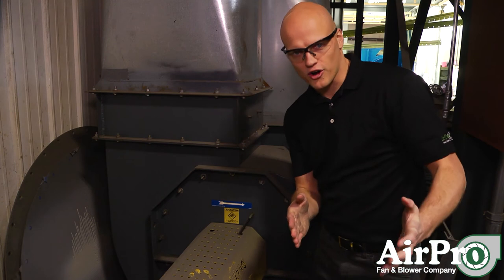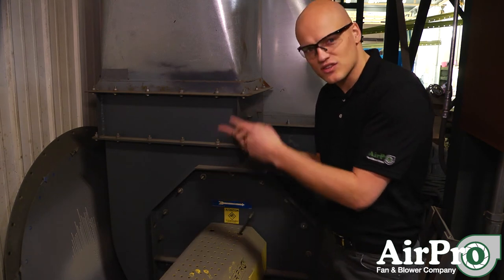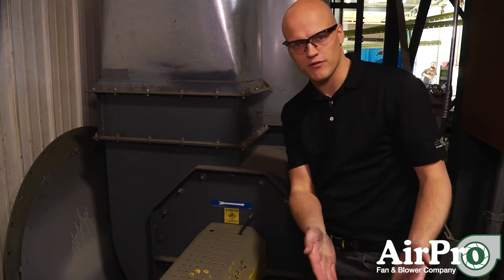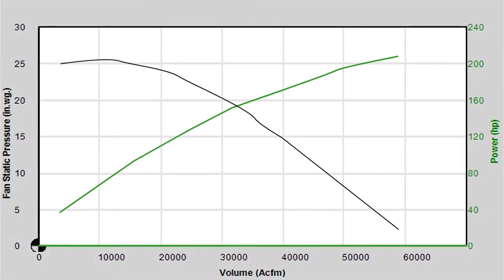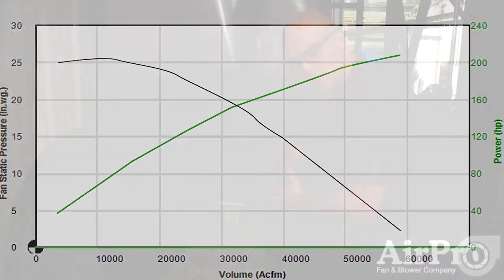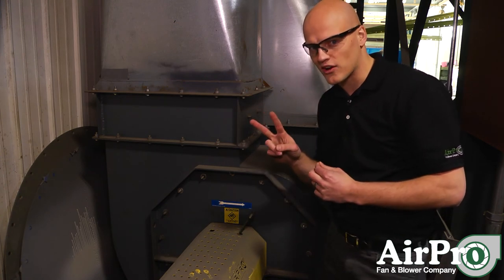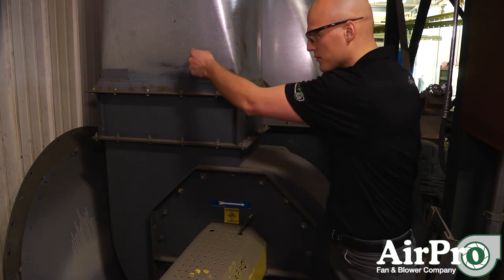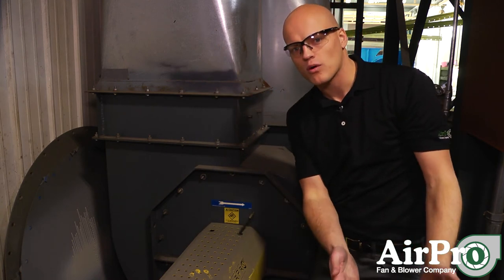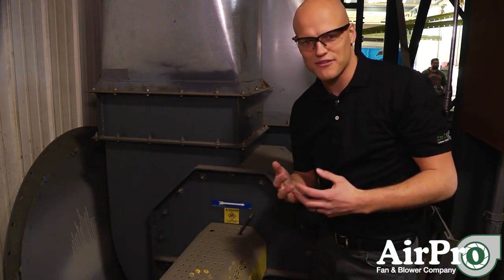You go to your fan curve expecting everything to line up, but when you look at it, 20 inches of static pressure going down the curve shows it should be taking 150 horsepower from your motor. So why does the discrepancy exist? We're going to assume your fan curve is accurate in terms of speed and gas density, yet the static pressure differential you're reading from your ports is not lining up with your motor horsepower. You're only doing 100 horsepower; you expected 150. What's the problem?